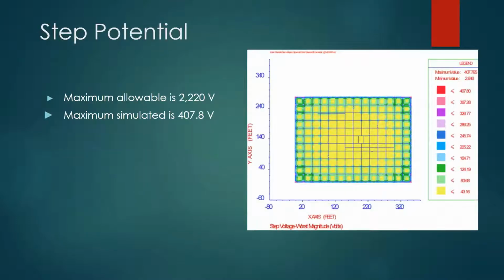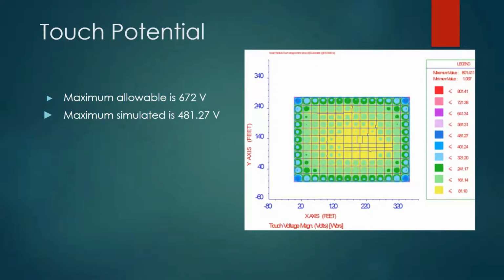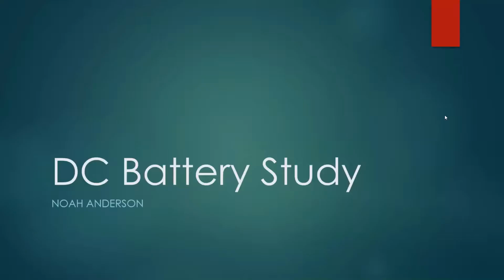So the grounding grid was simulated in a software called CDEGS. We were not able to do the simulation ourselves. Our sponsor had to do it, as a key of CDEGS cost $20,000. But for our step potential, the maximum allowable step potential, or the maximum safe step potential, would be 2,220 volts. In our substation, the maximum simulated is only 407.8 volts, so we are way below the limits in that area. For touch potential, the maximum allowable is 672 volts, and the maximum simulated is 481.27 volts. The best part about this is around our equipment in the middle of the substation, we're getting less than 81.1 volts of step potential.